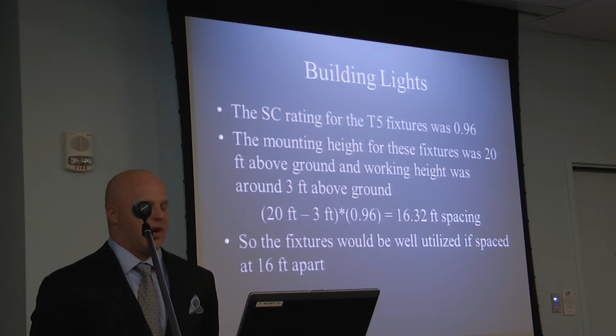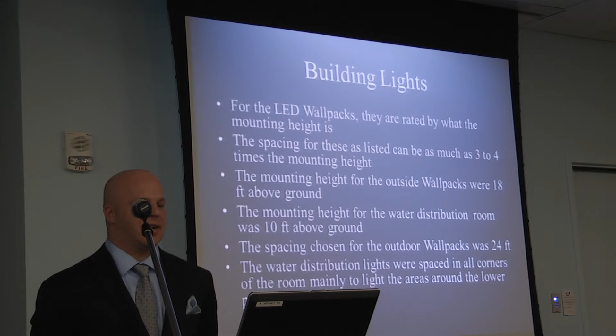For the LED wall packs used outdoors and in the water distribution area, those are rated by the mounting height as far as the wattage and as far as the spacing. The spacing for these is listed as being as much as 3 to 4 times the mounting height at the max. The mounting height for the outside wall packs was 18 feet above ground, and the mounting for the water distribution area wall packs was about 10 feet above ground. So for the outdoor wall packs, I chose spacing of about 24 feet. And the LED wall packs for the water distribution lights, I put in all 4 corners of the building to light the areas surrounding the water tank.